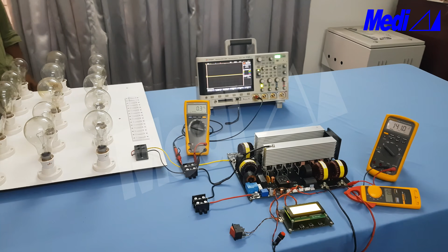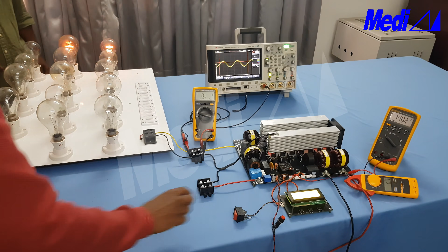Now let us conduct short circuit test from the battery. Mains not connected, battery connected. Switch on the inverter. See the AC output waveform. Let us short circuit. As you can see, nothing happens. Again, let's short circuit more than 4 to 5 seconds. Then it goes to cut off. Now inverter is shut down. We can restart it.